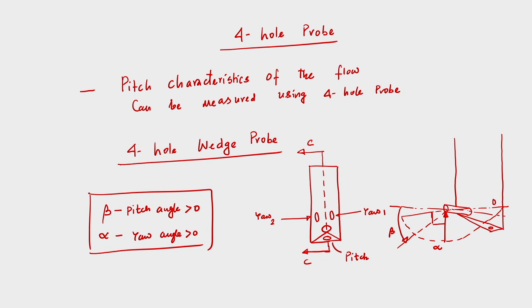We will see that when we measure flow parameters using 4 hole probes, there are 4 different holes we have identified. Now these holes are drilled radially, and the pressure taps are connected to the pressure leads, and those leads are connected to the U-tube manometer, rather two projection manometers and one U-tube manometer, and the U-tube manometer's two limbs are connected to the yaw orifices, that is point 2 and 3.